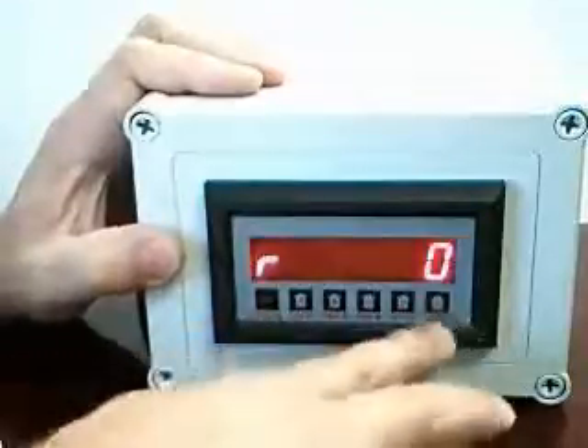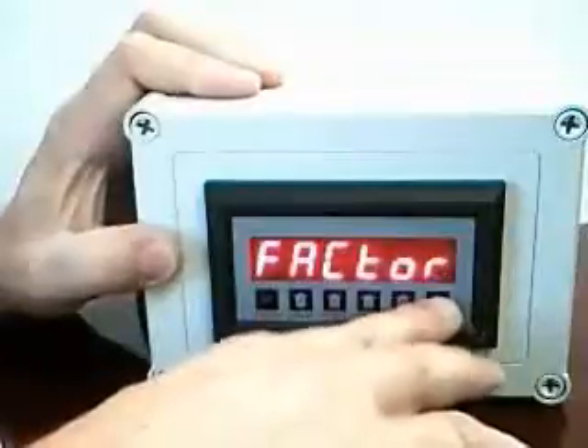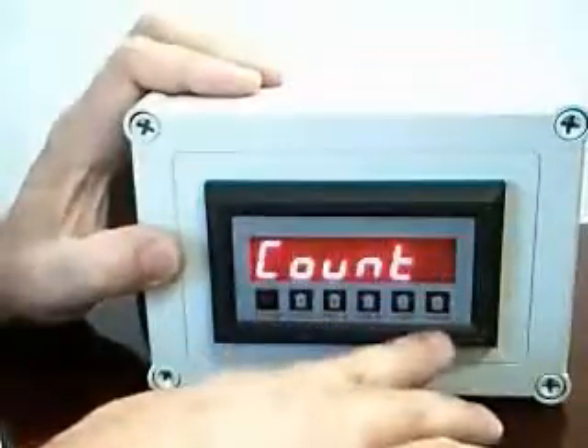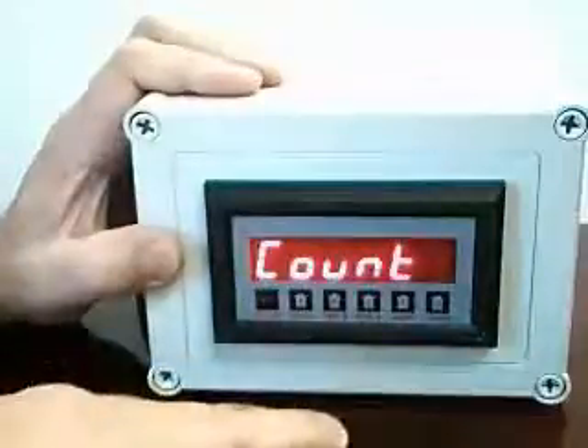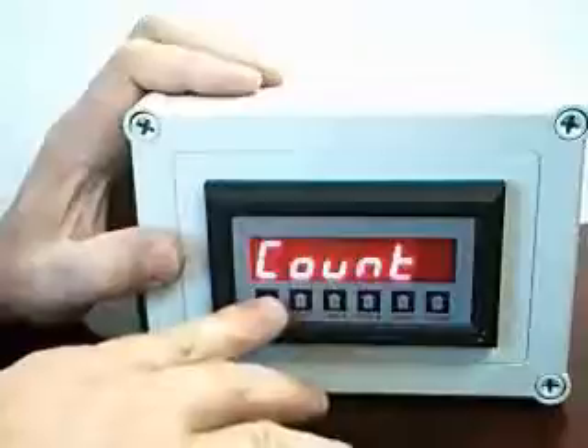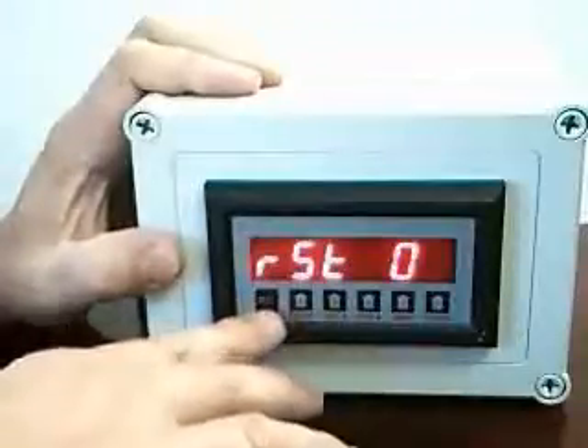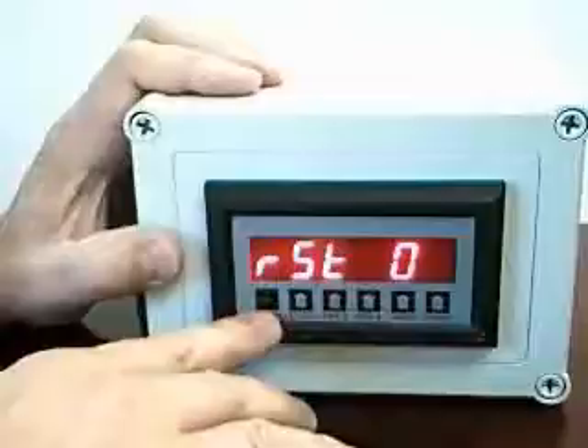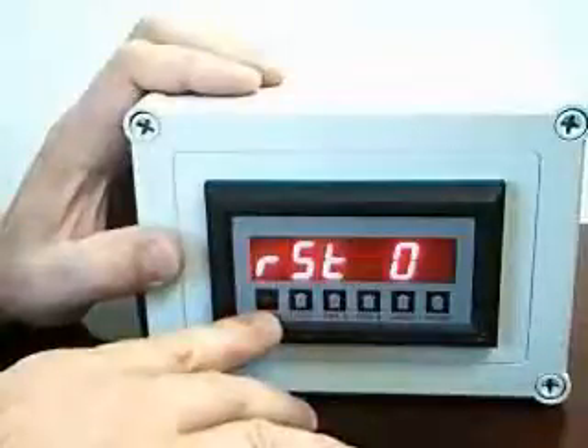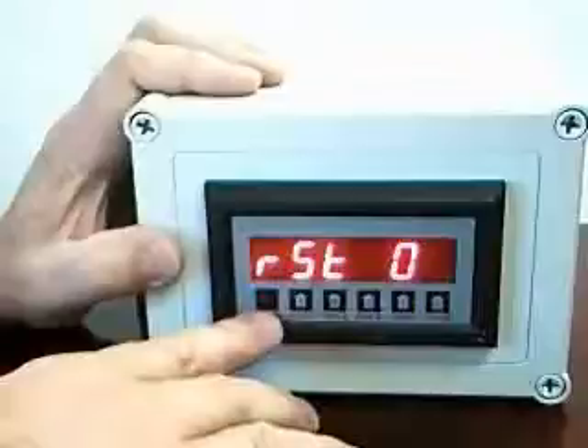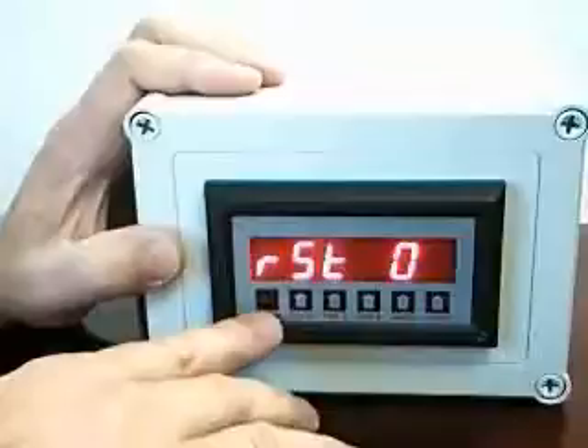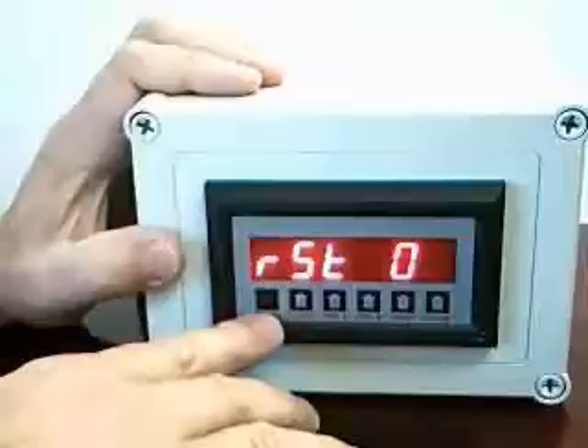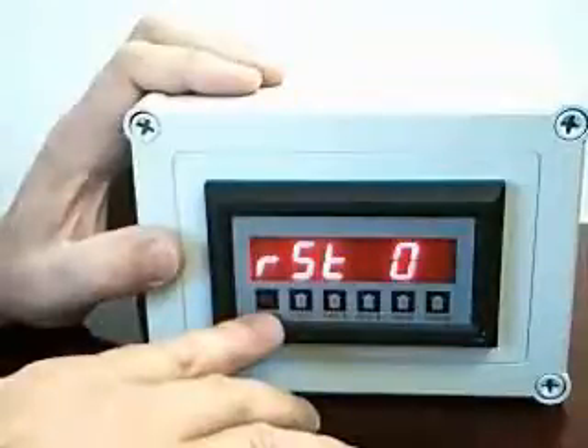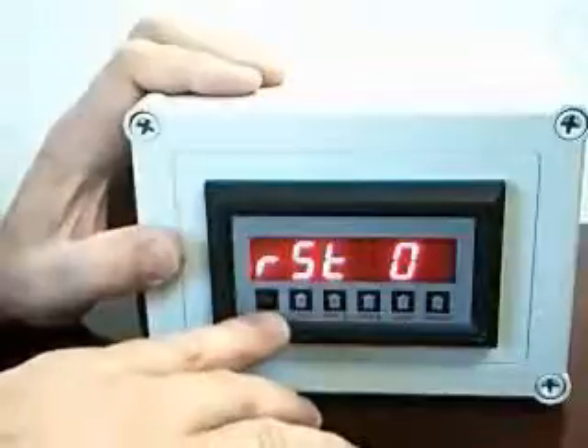So let's go to the second menu group now by pressing the program button twice until I'm at the count submenu group. I'm now going to hit Enter to go into that submenu group, and my first selection here says RST0, and this is how the instrument will respond when the reset button is hit. It'll reset the total to 0. This corresponds to a mode where the totalizer will begin at 0 and count up from that point. This is the most common in a totalizer application.